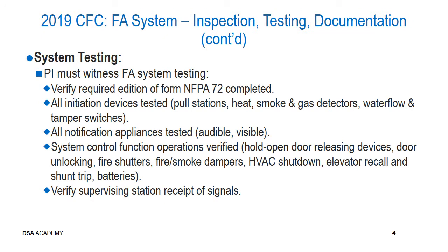In addition, the project inspector should be witnessing the testing to verify that the standard test form from NFPA 72 has been completed and provided to the project inspector, that all initiation devices were tested. That includes pull stations, heat, smoke, and any gas detectors, water flow switches, and tamper switches. Testing will include all notification appliances being tested, making sure that they are both audible and visible.